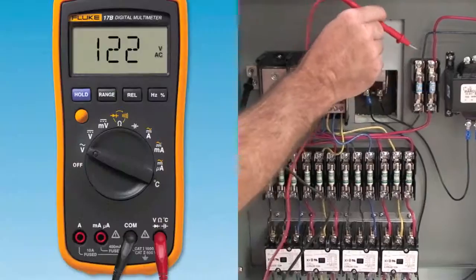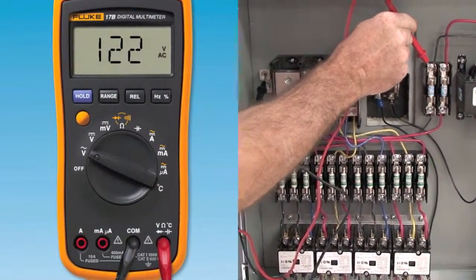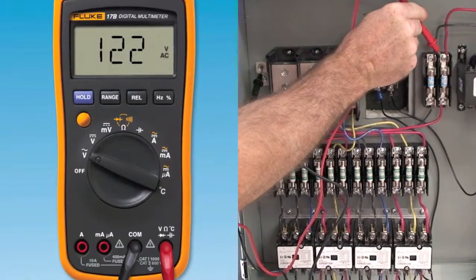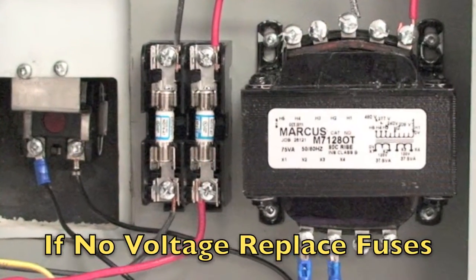If voltage is present, move lead to upper L1 and L2 terminals and verify 120 volts AC. If no voltage is present, replace fuse or fuses.